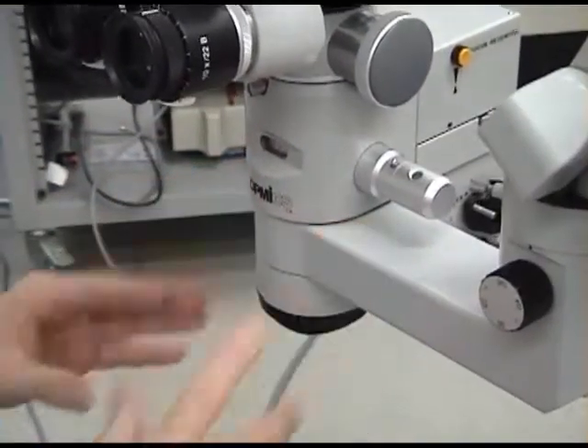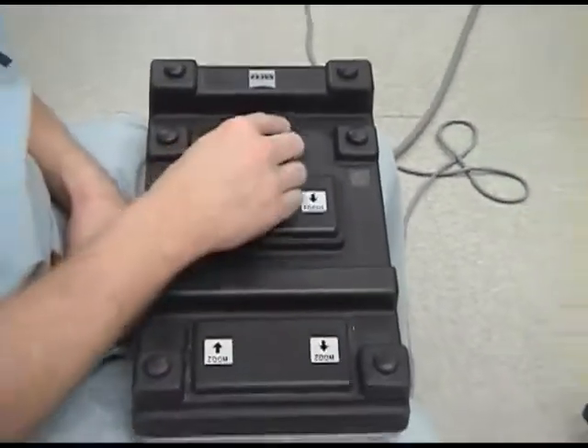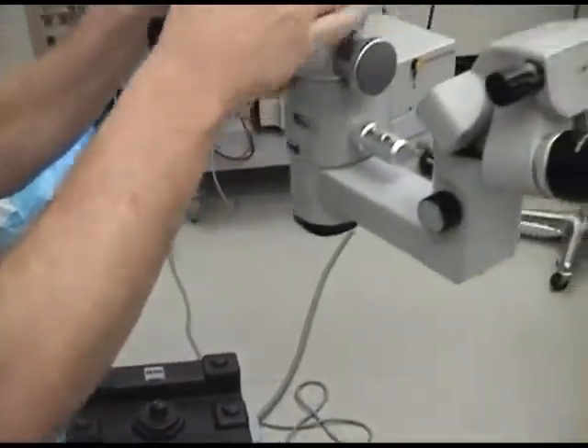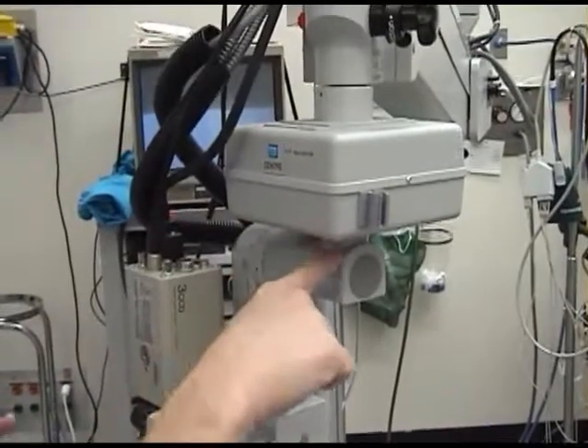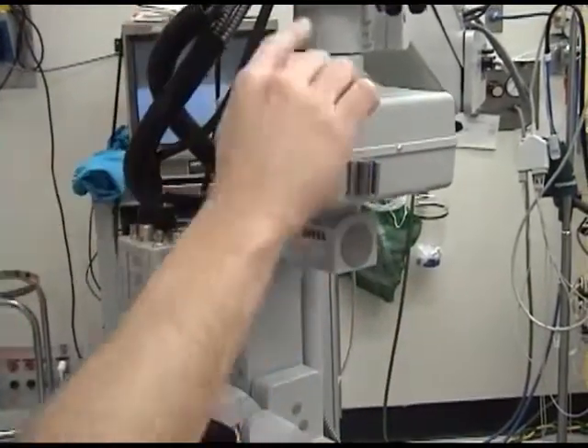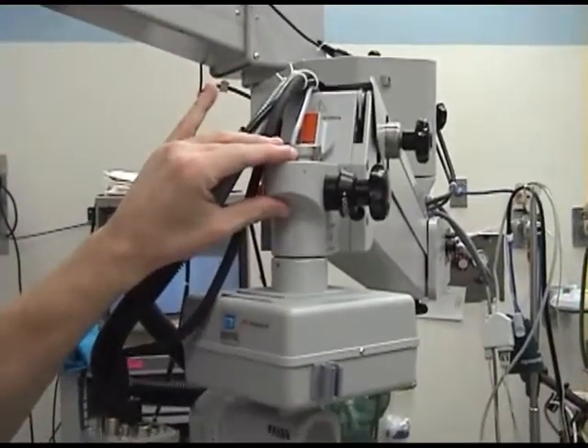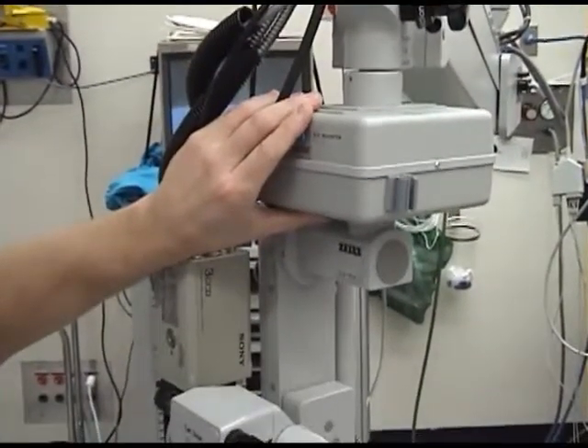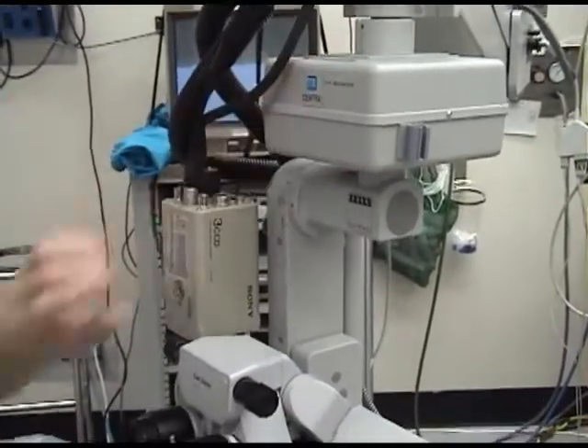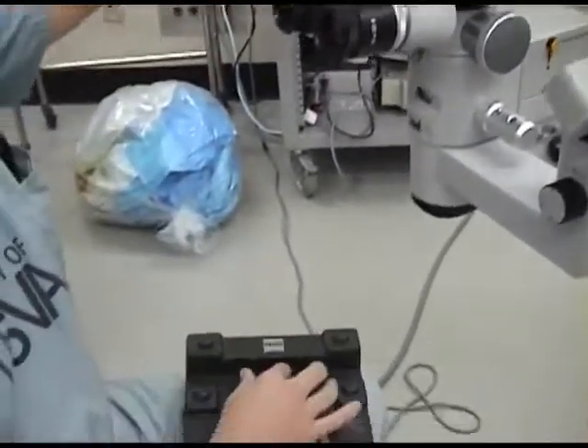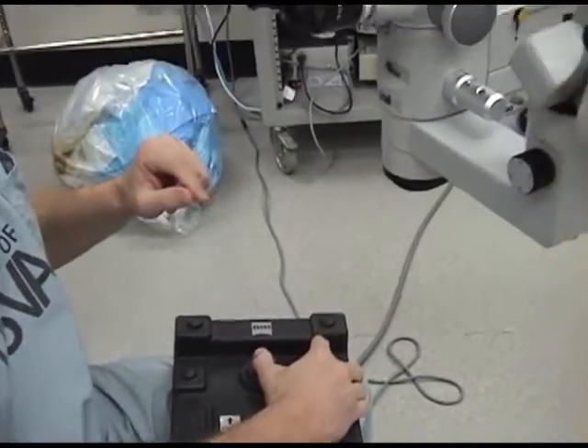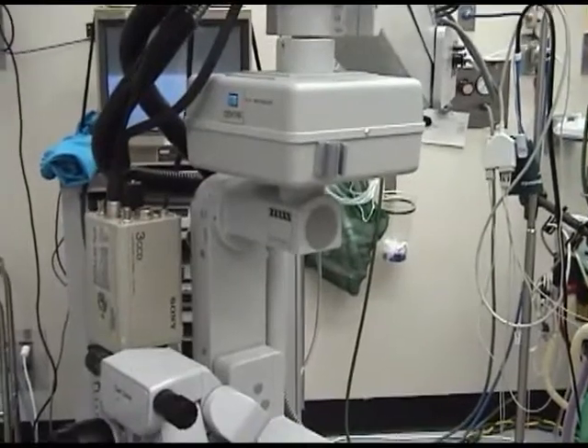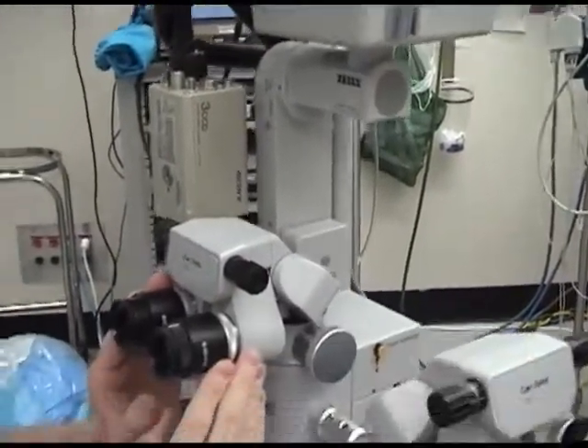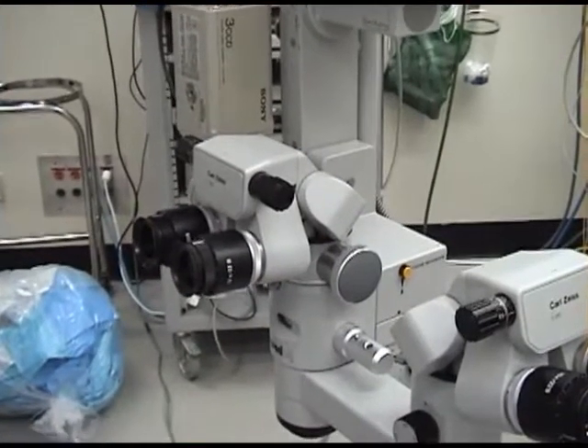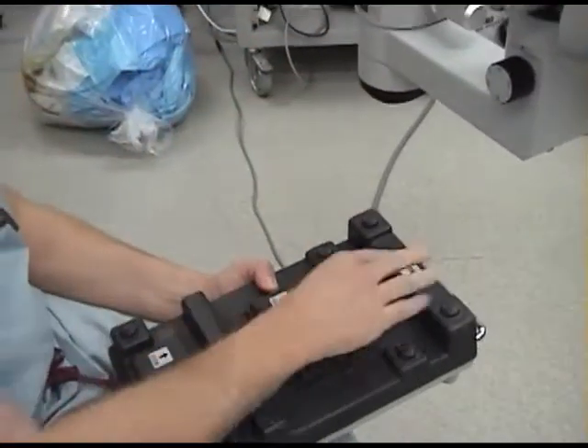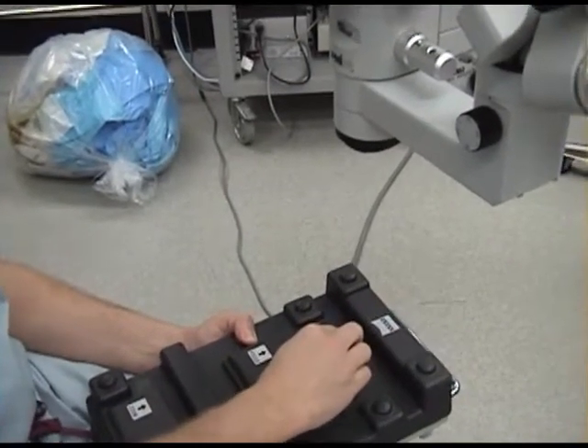Okay, so in addition to the ability to zoom and focus with these pedals, there's also an XY. What you do at the start of the case is you push the XY, you saw it just centers it. So that centers the microscope in this box relative to the stand. And now, if you want to make subtle variations in where the microscope is, you use this little joystick with your toes and you move it around. You can see how it's moving to the left or to the right. Now these positions left and right are always relative to the surgeon microscope. So you have to keep that in mind and keep this foot in the same direction as the surgeon, so that when you go up, the microscope goes up, when you go down, the microscope goes down.